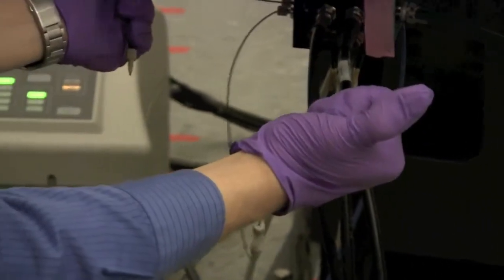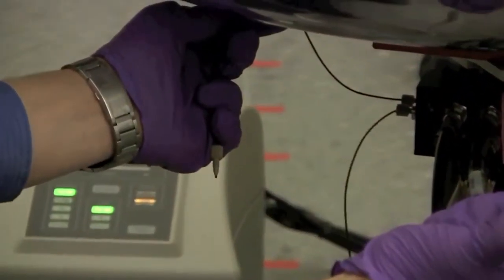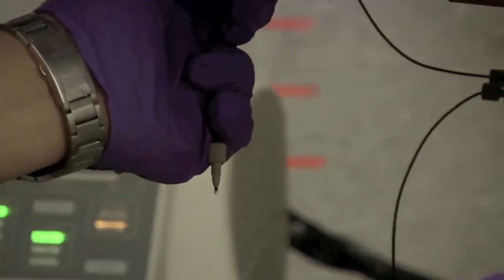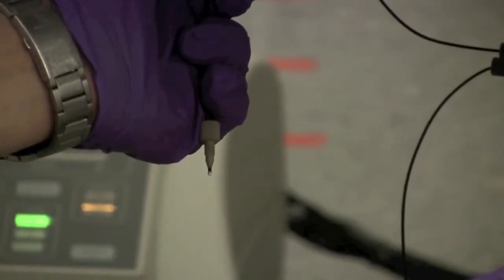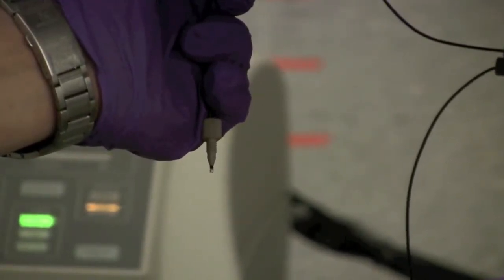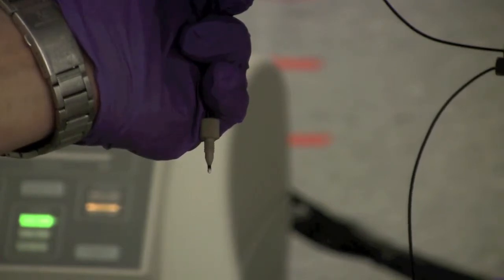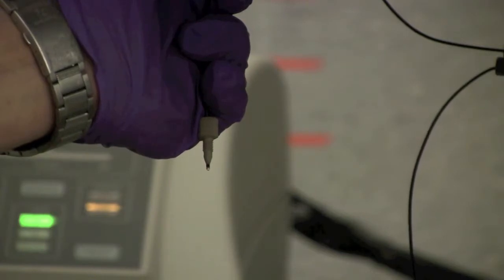Different solvents have different viscosities. Acetone has relatively low viscosity, so the back pressure will be less on it. The chloroform's got a little bit higher viscosity, so it will have a little bit higher back pressure on it as you push it through. It's going through fairly nicely though.